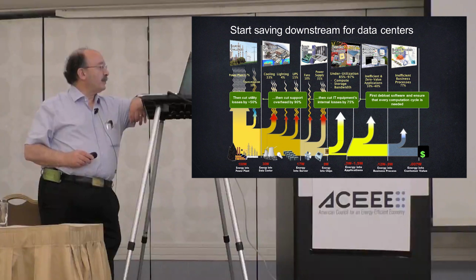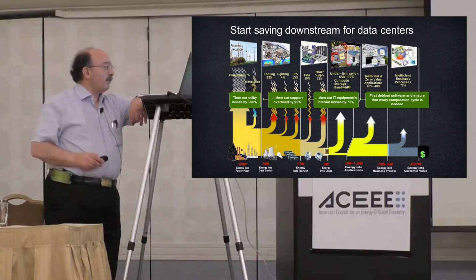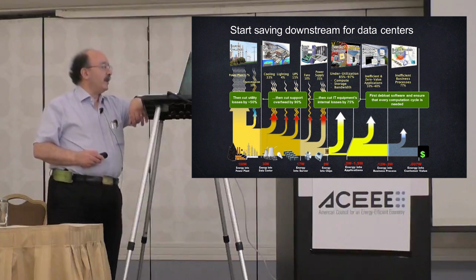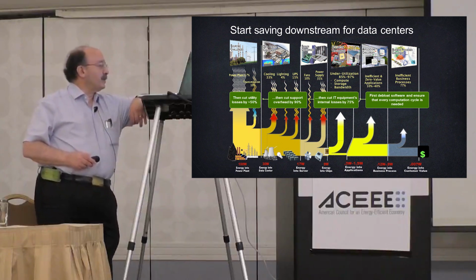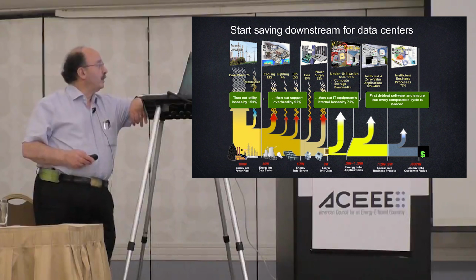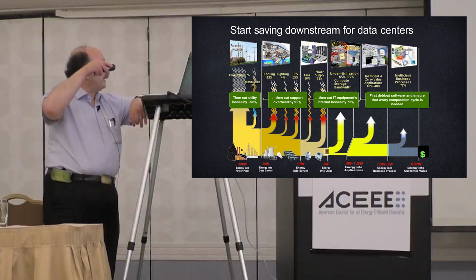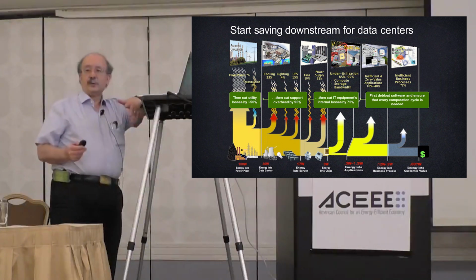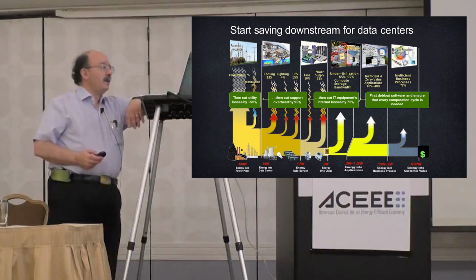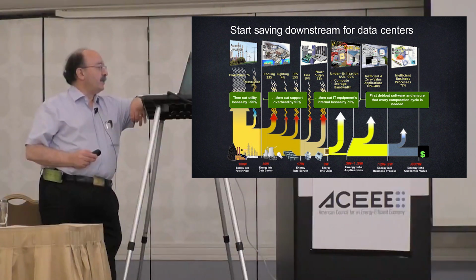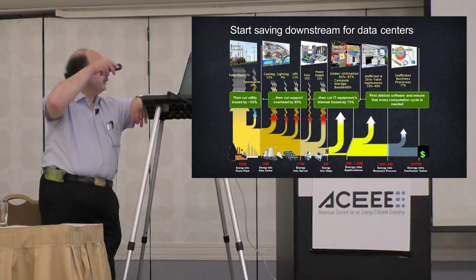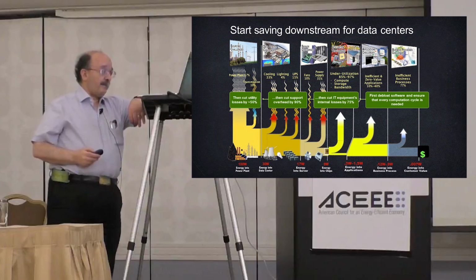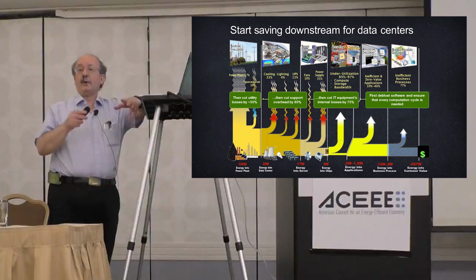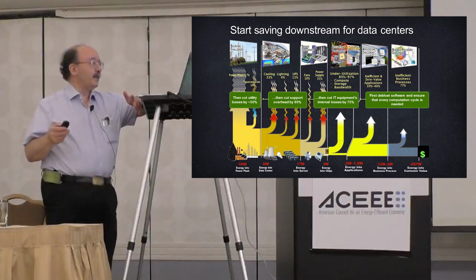For example, two-thirds of the fuel fed into the power plant is lost in the plant and the grid, and then half the metered electricity is lost before it gets to the servers, running mainly the cooling and uninterruptible power supplies, which together are half the capital cost. And then half the energy that reaches the servers doesn't get to the chips because it's lost in inefficient, usually very part-loaded power supplies, and a lot of fans taking heat that largely shouldn't be there off the motherboard into the room, so we can do dumb things with it.